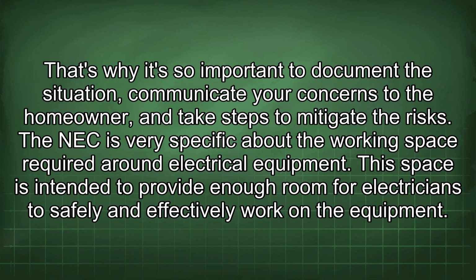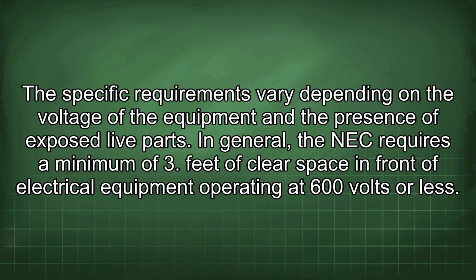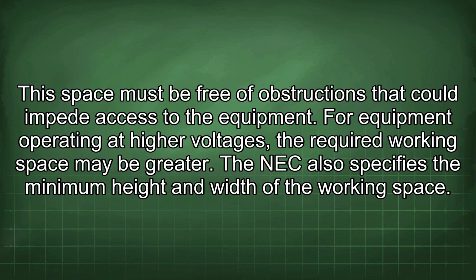The NEC is very specific about the working space required around electrical equipment. This space is intended to provide enough room for electricians to safely and effectively work on the equipment. The specific requirements vary depending on the voltage of the equipment and the presence of exposed live parts. In general, the NEC requires a minimum of 3 feet of clear space in front of electrical equipment operating at 600 volts or less. This space must be free of obstructions that could impede access to the equipment. For equipment operating at higher voltages, the required working space may be greater.